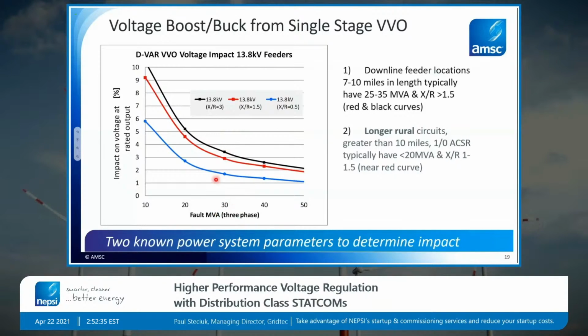So let's take an example. 30 MVA fault power, which might be pretty common about 7-8 miles down a feeder. And then very common conductor sizes, X over R's, are in this range at 1.5 to 3. And so on that portion of the feeder, the STATCOM can buck or boost by plus minus 3%. If we go to a more common long feeder example, so let's say more than 10 miles out, we're more commonly now going to be on the left portion of this graph. And we can see one VVO STATCOM can buck and boost by plus minus 5% on those longer locations.